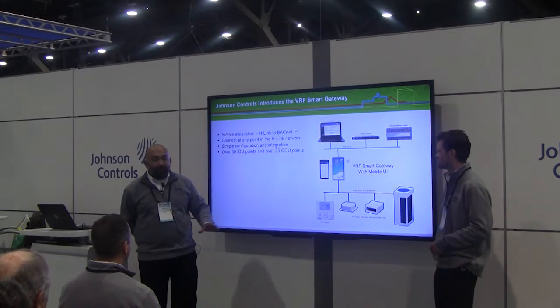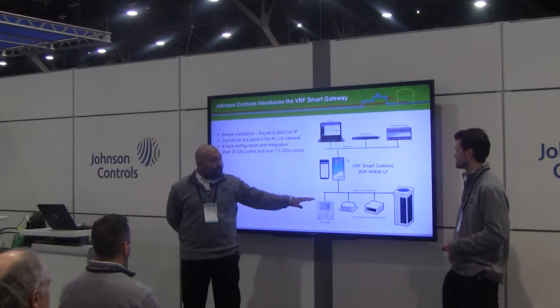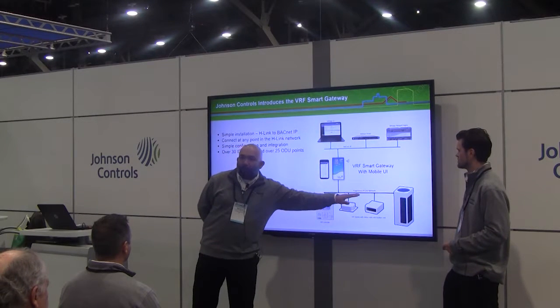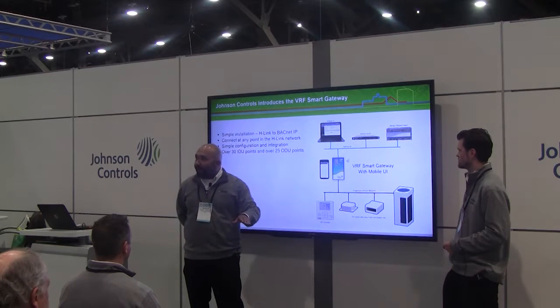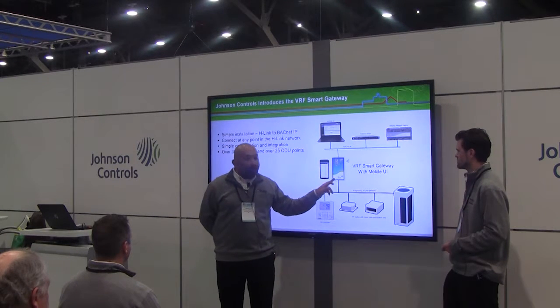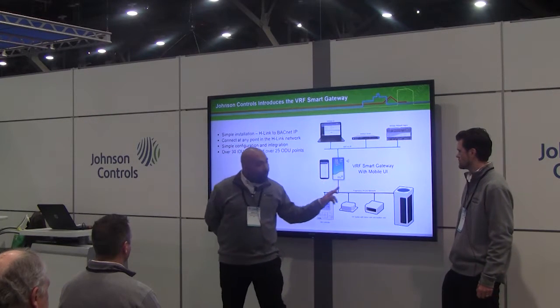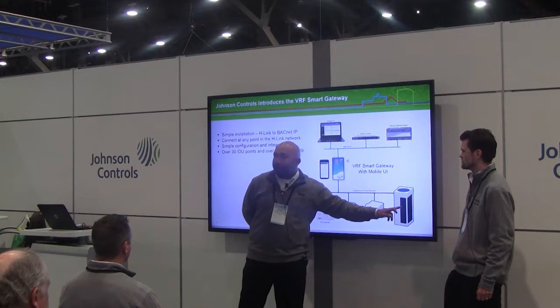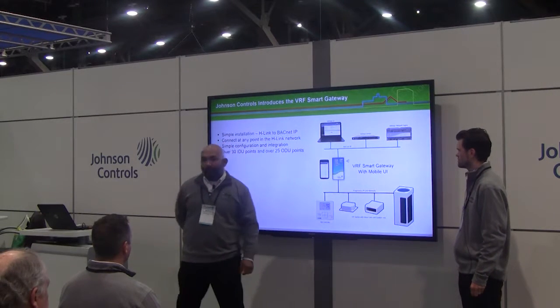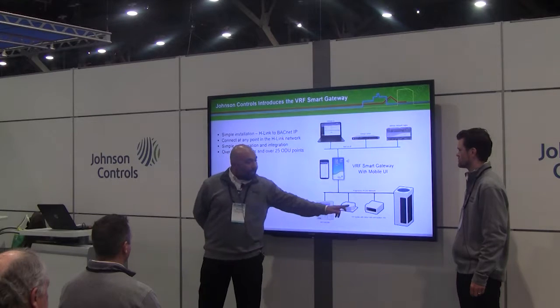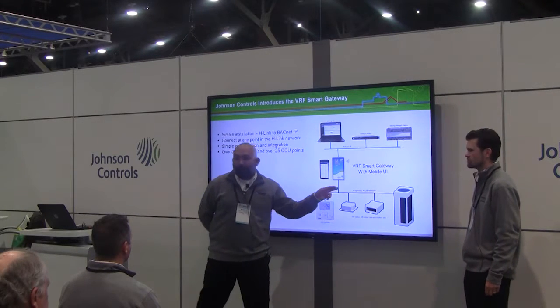One of the major benefits of this adapter is that we can connect it anywhere in our H-Link system. With other manufacturers, you actually have to take the wire from your adapter all the way out to your outdoor bank of units. And if you're 500 feet away, you have to run a 500-foot cable. Now we can land this at any indoor unit in our daisy chain.